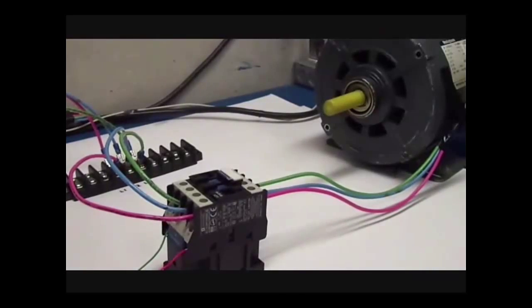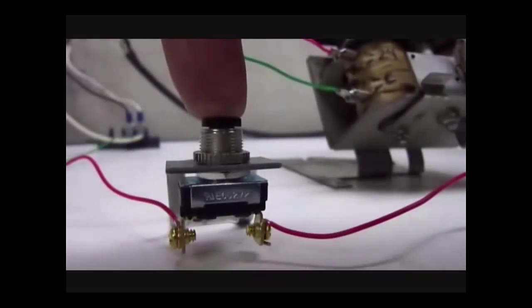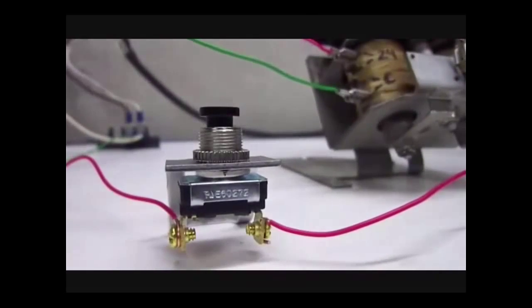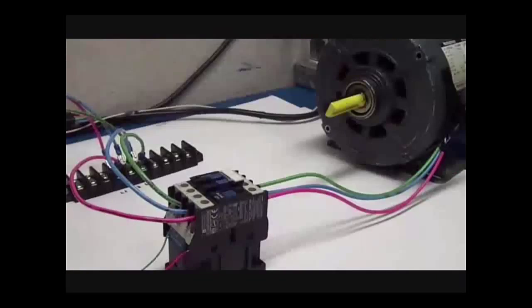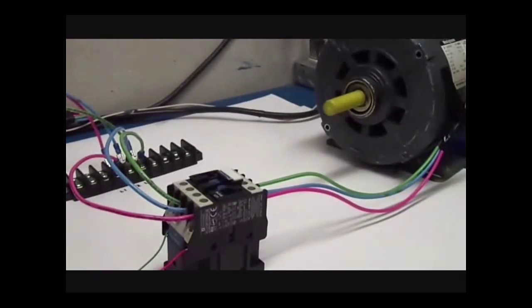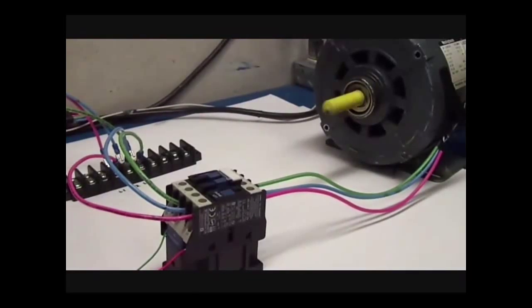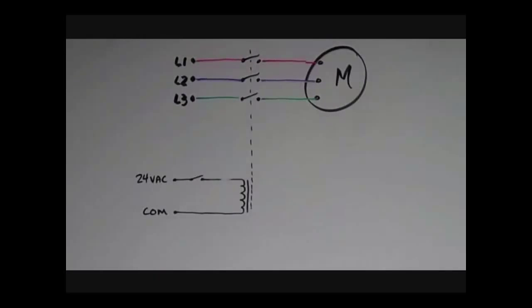And there you have it. I can use a cheesy little single pole switch that's only rated for 1/4 of an amp to run a 3-phase 460 volt motor that runs at 20 amps. Here's the schematic for what we've done so far.